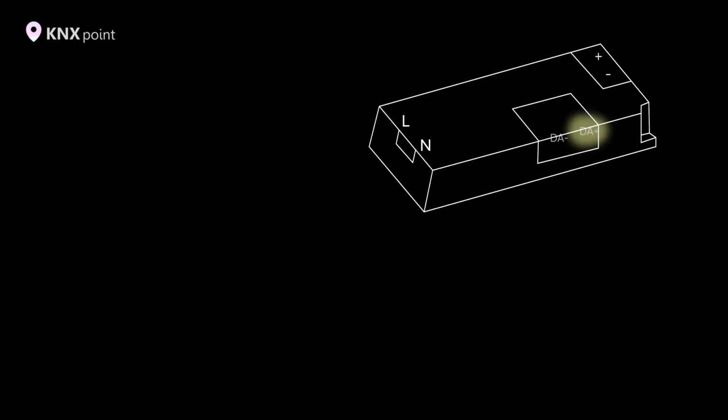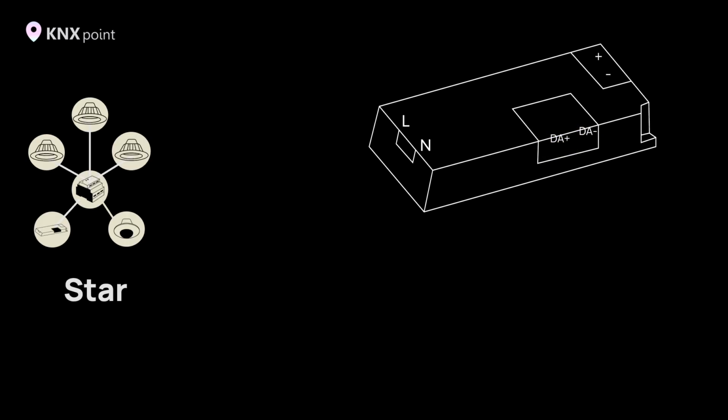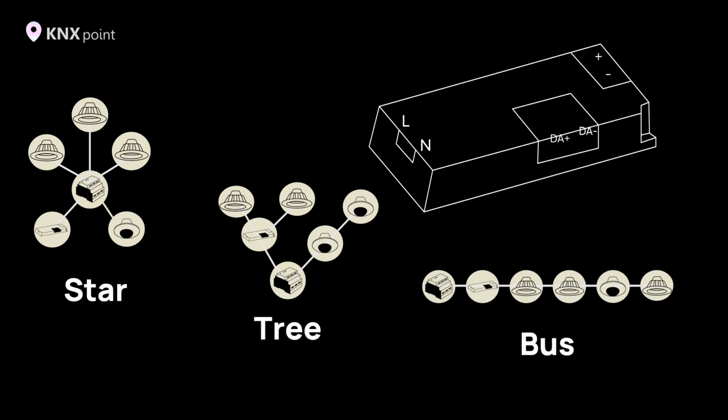When connecting devices to the bus, strict polarity observance is not required, with rare exceptions. Any topology except a ring is allowed for the DALI bus. Typically, the topology is a tree topology, combining a bus topology and star topology.